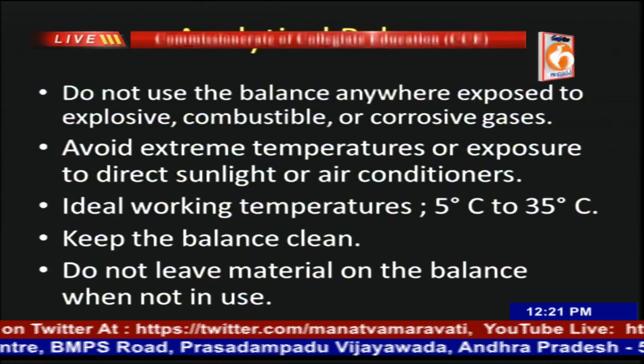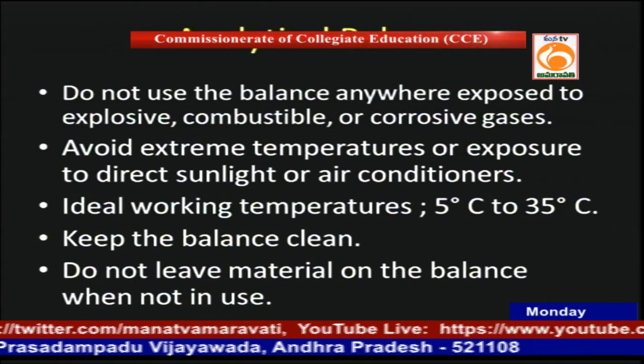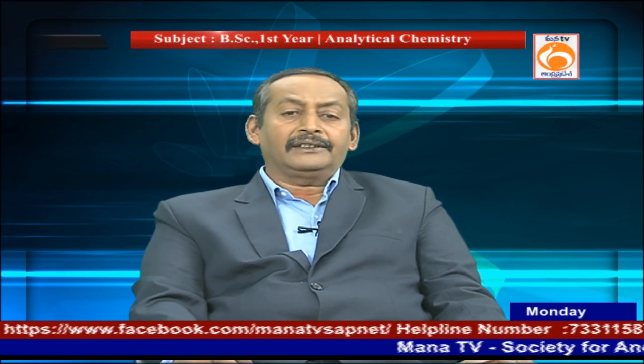Do not use the balance anywhere exposed to explosive, combustible or corrosive gases. It's natural, because the reason for writing corrosive is that there is a metal structure inside, and there is a possibility for corrosion and it gets corroded. So there are possibilities of error. Because of this, certain suggestions have been given here, and an operating temperature of 5 to 35 is also recommended.